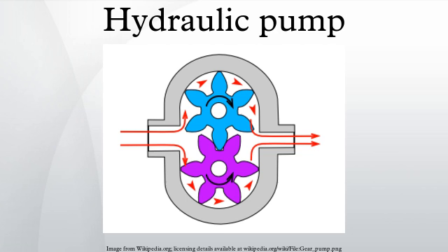Pumps for open and closed systems. Most pumps are working in open systems. The pump draws oil from a reservoir at atmospheric pressure. It is very important that there is no cavitation at the suction side of the pump. For this reason the connection of the suction side of the pump is larger in diameter than the connection of the pressure side. In case of the use of multi-pump assemblies, the suction connection of the pump is often combined.